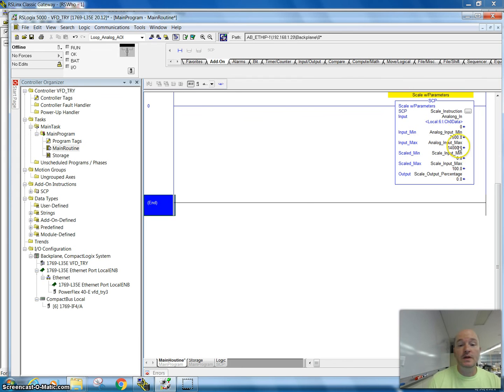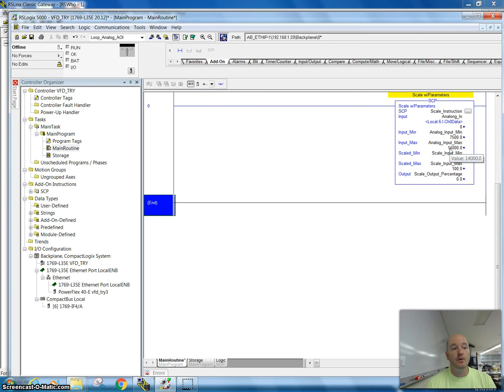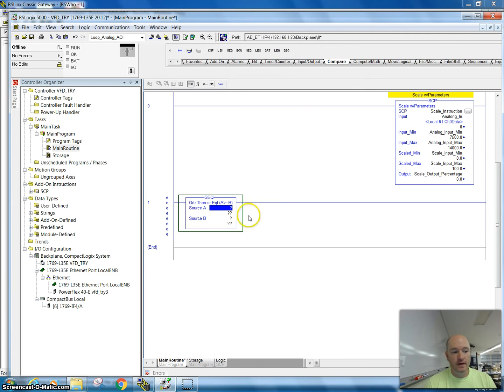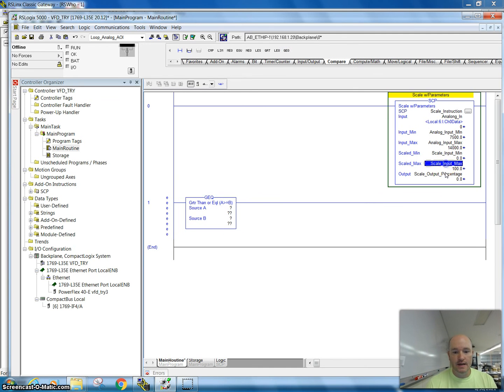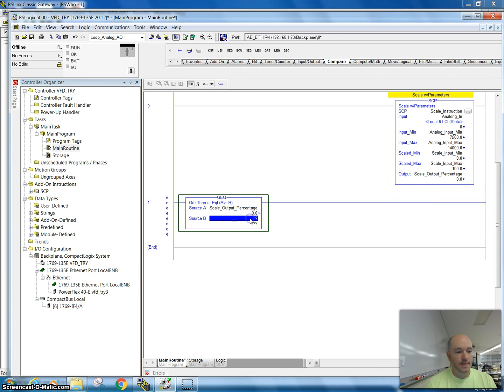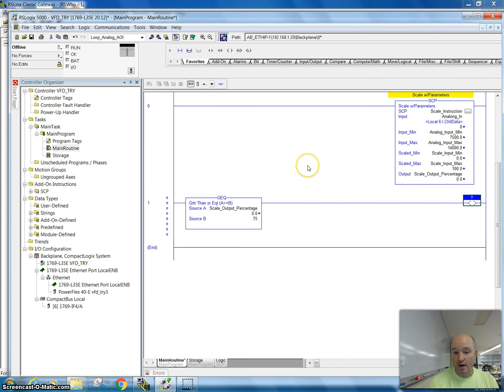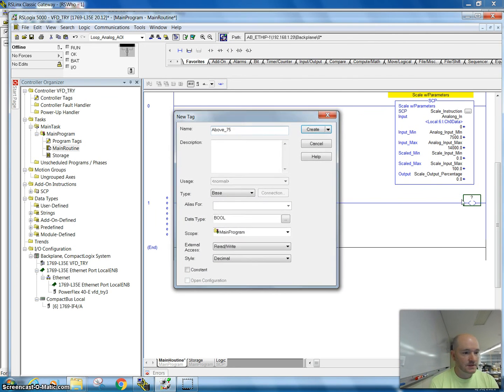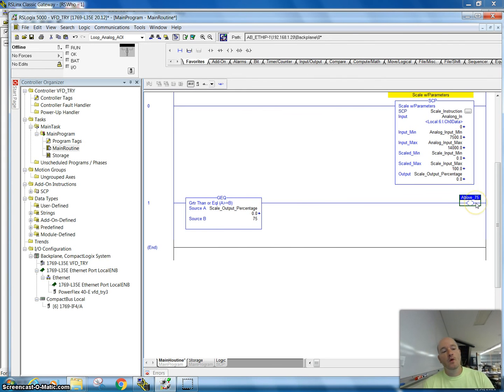The next thing we want to do is — what do we do with this output? Right now we're not doing anything with it; it's just converting to a percentage. So let's say I'm going to tie this to an HMI for graphics. If I wanted to control something with it, I might throw in a compare instruction — a greater-than-or-equal-to. I'll use my scale output percentage, and let's say at 75% I want a warning light to come on. I'll create a quick tag called 'above 75', and this will go on when we reach that point.